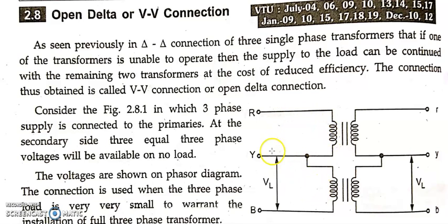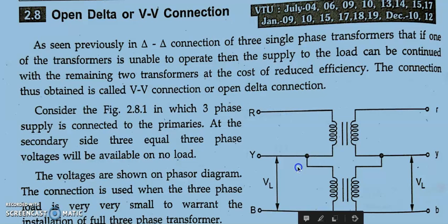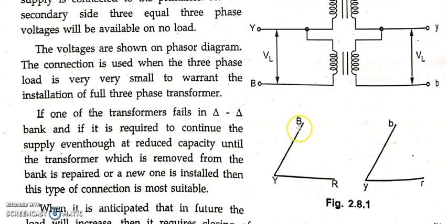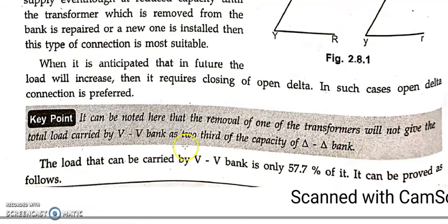So by making such a connection, you can give three-phase supply to these two single-phase transformers, as well as take three-phase supply out of them, but at reduced efficiency or reduced kVA. So this is the phasor diagram we have. If I remove one of the single-phase transformers, it is the same for primary as well as secondary. So like I told you, it is not 2/3. Yes or not? It is around 57.7%. If I do 2 by 3 and take the percentage, I will get 66.67, but here it is not so. You are actually supposed to use 57.7% of the total kVA.